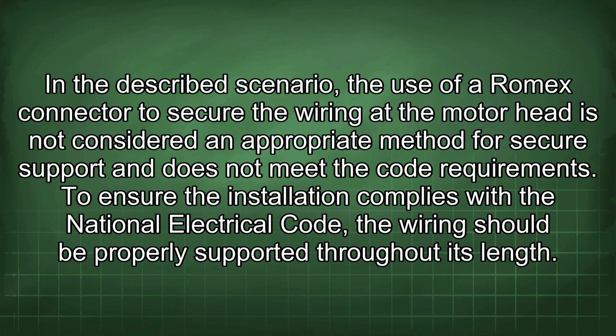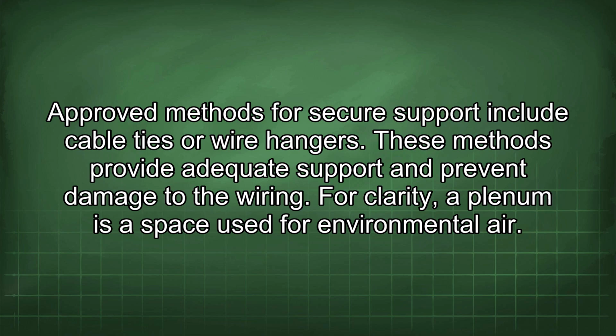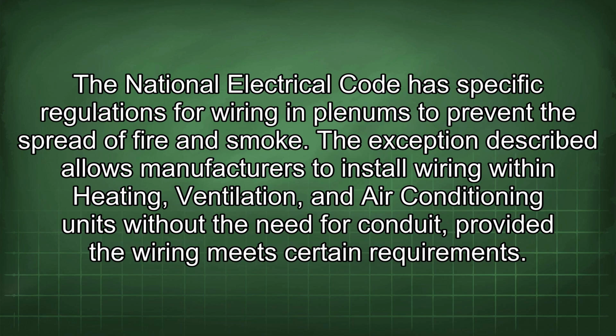To ensure the installation complies with the National Electrical Code, the wiring should be properly supported throughout its length. Approved methods for secure support include cable ties or wire hangers. These methods provide adequate support and prevent damage to the wiring. For clarity, a plenum is a space used for environmental air. The National Electrical Code has specific regulations for wiring in plenums to prevent the spread of fire and smoke. The exception described allows manufacturers to install wiring within heating, ventilation, and air conditioning units without the need for conduit, provided the wiring meets certain requirements.